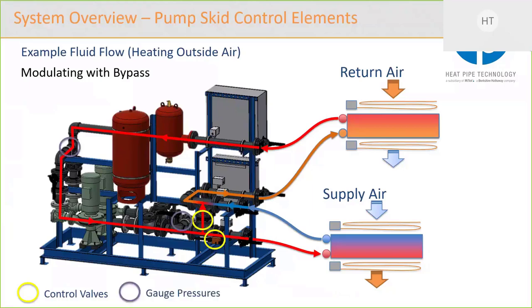We're also measuring gauge pressures before and after the pumps, and that's used for two reasons. It's to make sure that the suction pressure on the pump is sufficient to avoid cavitation, and it's used to calculate differential pressure to prove that the pumps are actually creating a head.